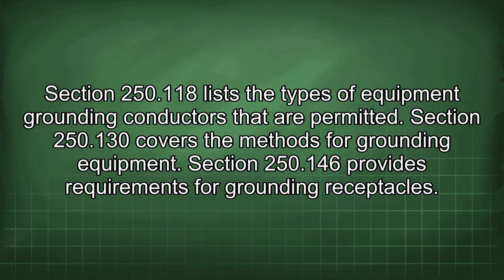Section 250.118 lists the types of equipment grounding conductors that are permitted. Section 250.130 covers the methods for grounding equipment. Section 250.146 provides requirements for grounding receptacles.